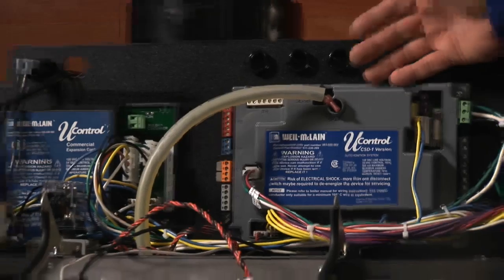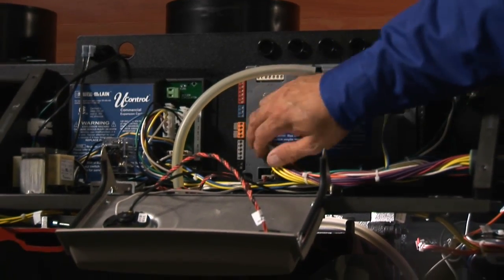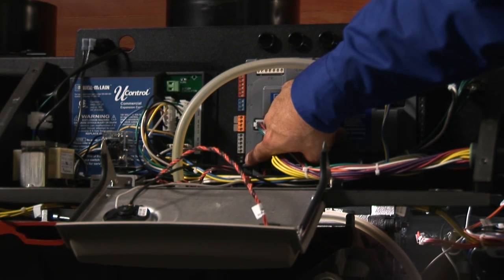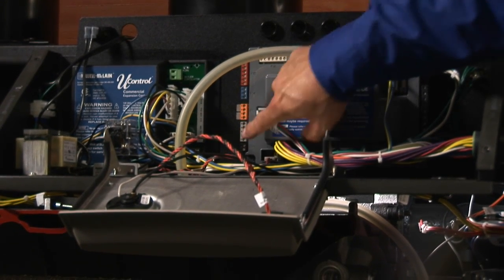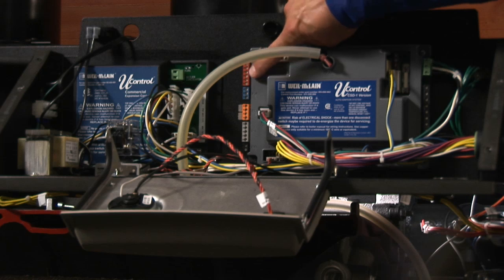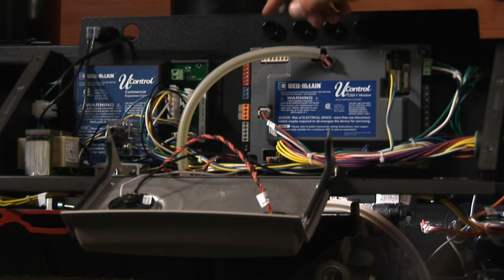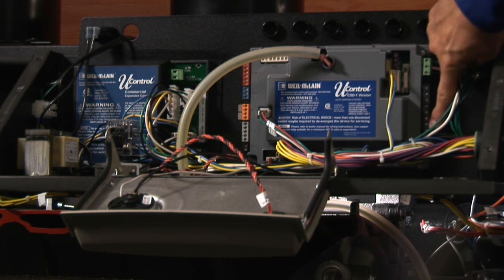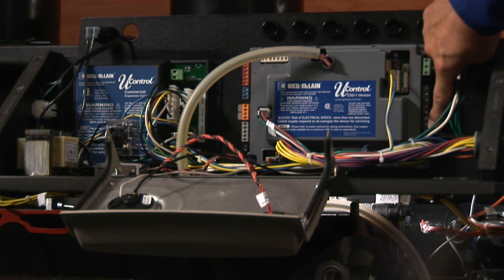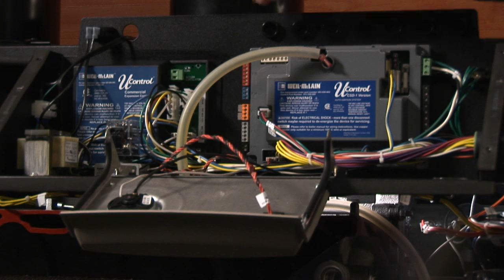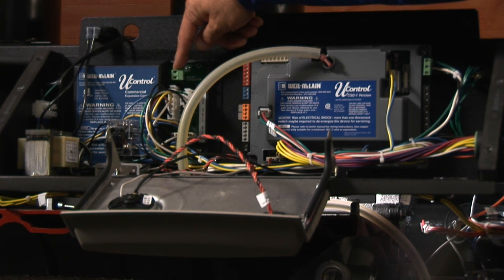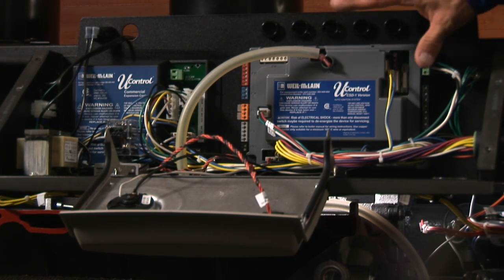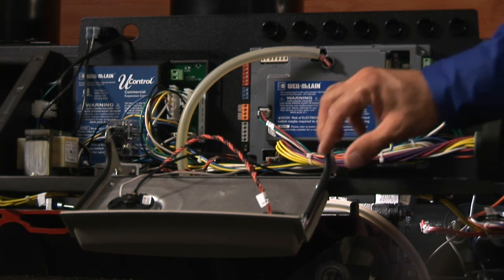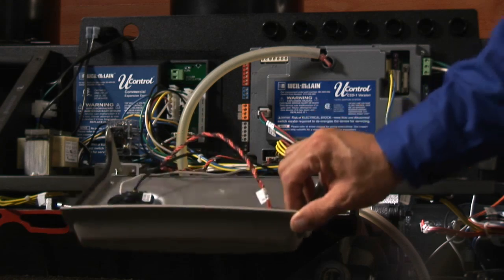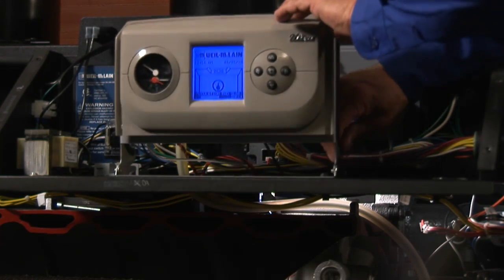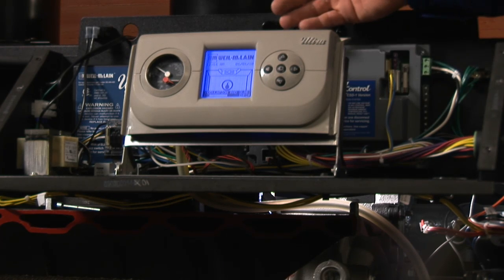A heat, hot water input, whatever you want to run off the boiler, you're going to do it the same way. Outdoor sensor comes with the boiler. First input would be here, second input would be here, third input would be here. So you have the capability of 3 inputs and 3 outputs of 2.2 amps each, and then the 1 10 amp output for the boiler pump is going to be right here. So everything on the U-control we reused and wanted it to be exactly the same as the residential model to try to make everyone's job a little easier in the field in transitioning from the residential marketplace to the commercial marketplace.